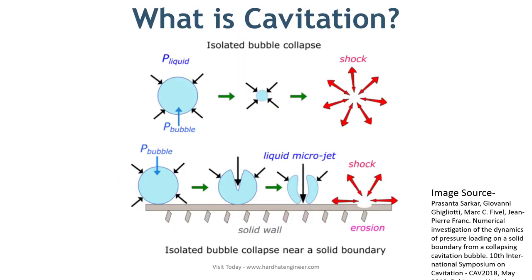What is cavitation, and why do you have to know about it? Have you ever seen a pump that makes a sound like it is transporting marble and gravel? Cavitation is responsible for such high sound and vibration in the pump. When vapor bubbles are created inside the pump and subsequently collapse inside the pump, that is known as cavitation.